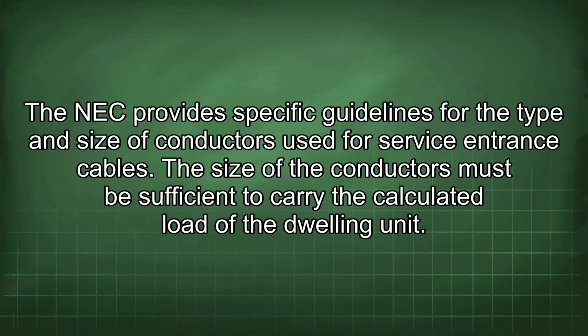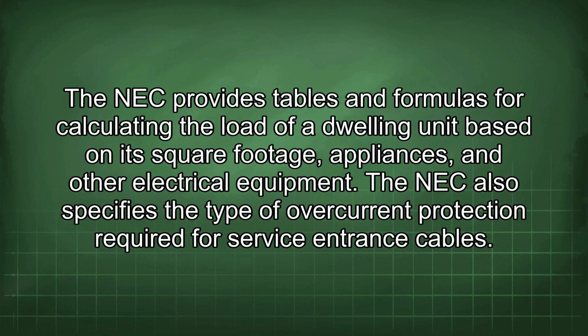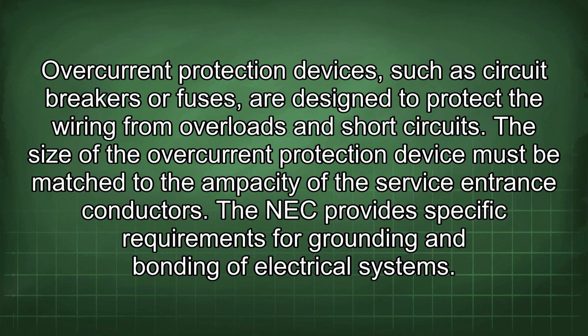The NEC provides specific guidelines for the type and size of conductors used for service entrance cables. The size of the conductors must be sufficient to carry the calculated load of the dwelling unit. The NEC provides tables and formulas for calculating the load of a dwelling unit based on its square footage, appliances, and other electrical equipment. The NEC also specifies the type of overcurrent protection required for service entrance cables. Overcurrent protection devices, such as circuit breakers or fuses, are designed to protect the wiring from overloads and short circuits. The size of the overcurrent protection device must be matched to the ampacity of the service entrance conductors.